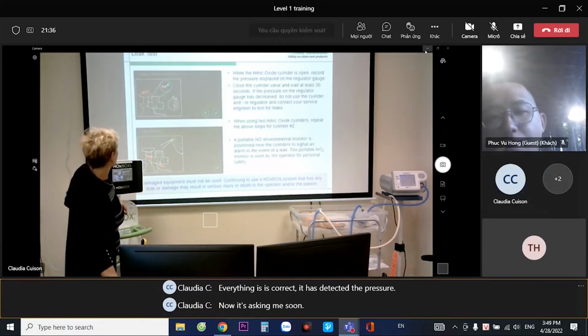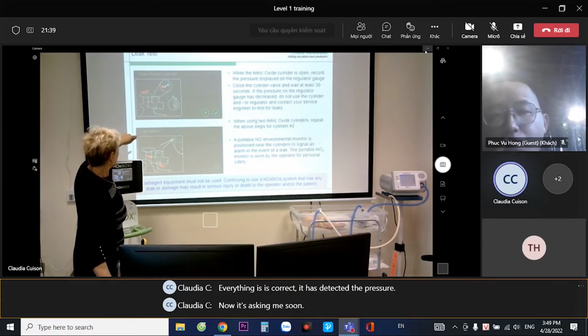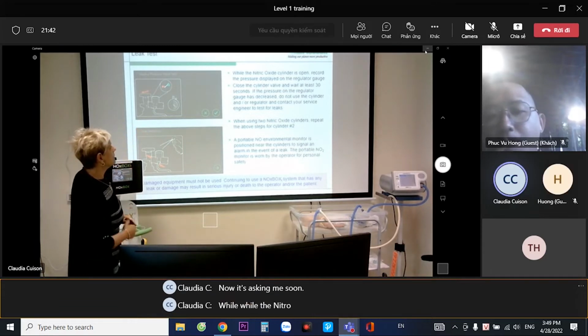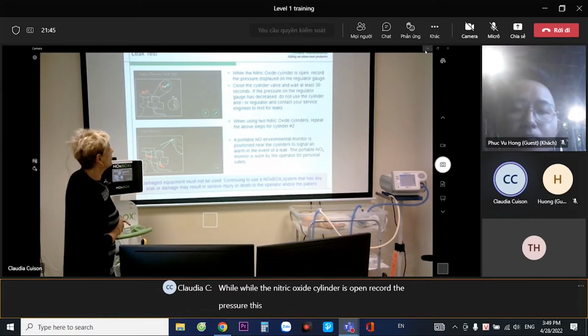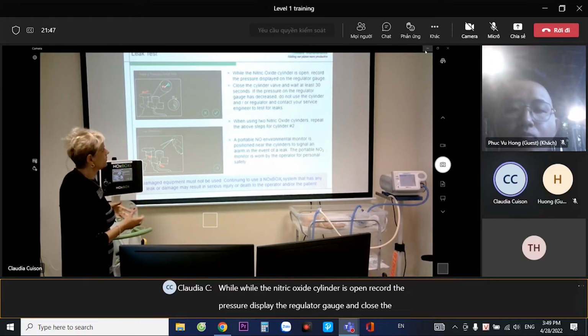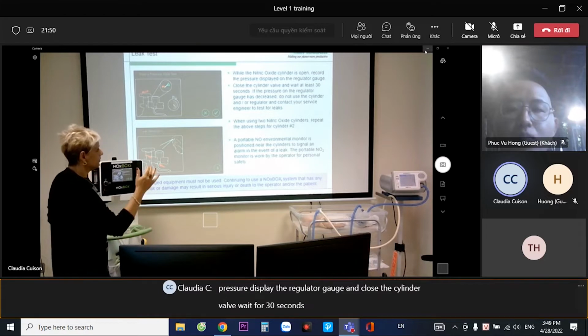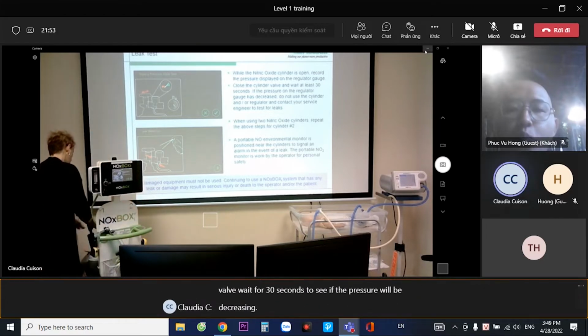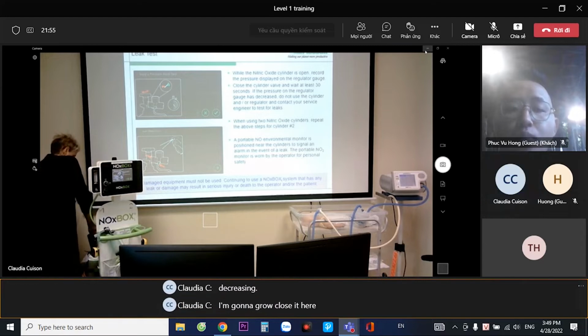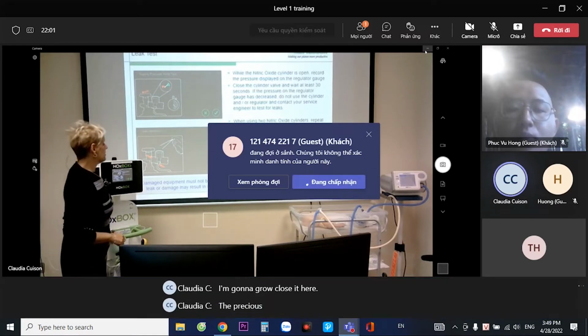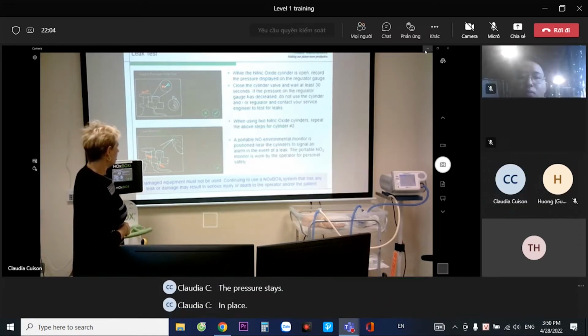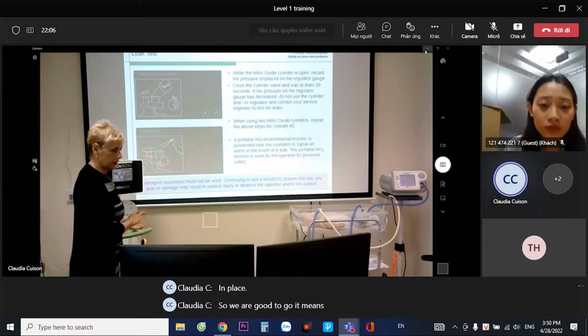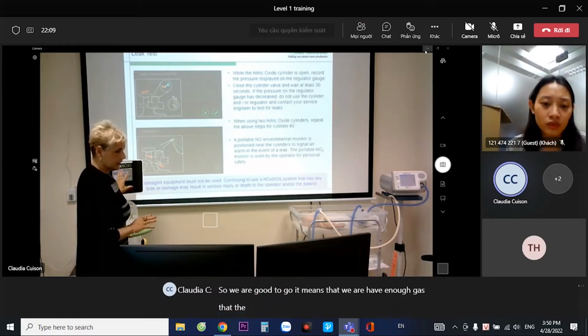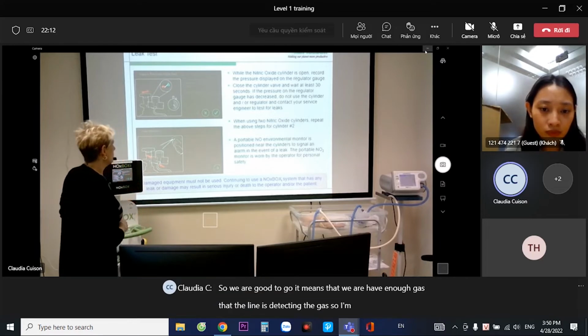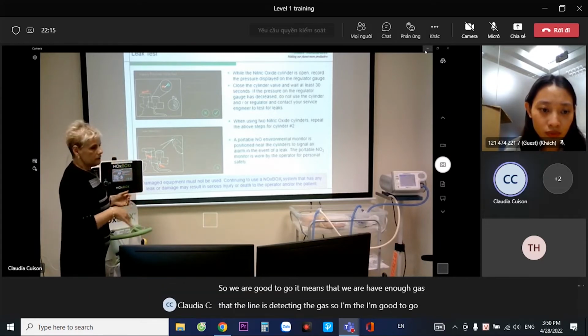Now it's asking me to, while the nitric oxide cylinder is open, record the pressure displayed on the regulator gauge and close the cylinder valve. Wait for 30 seconds to see if the pressure will be decreasing. So I'm going to close it here. The pressure stays in place. So we are good to go. It means that I have enough gas, that the line is detecting the gas, so I'm good to go.